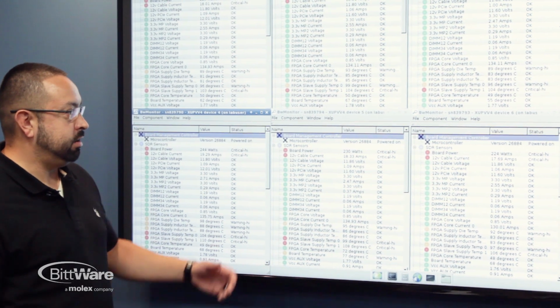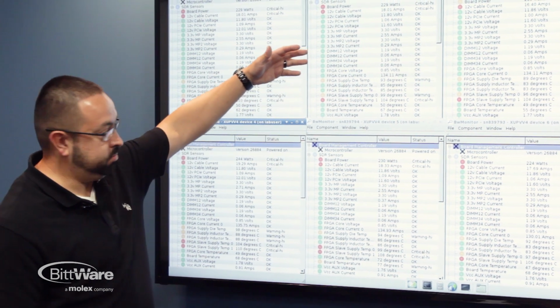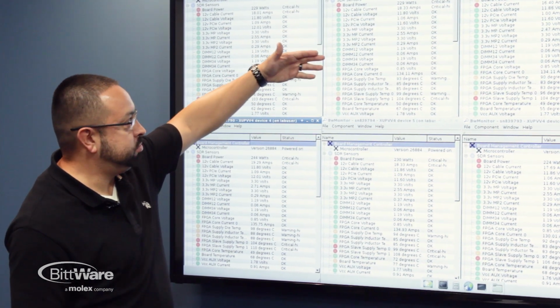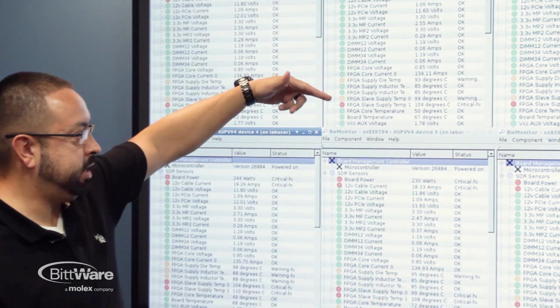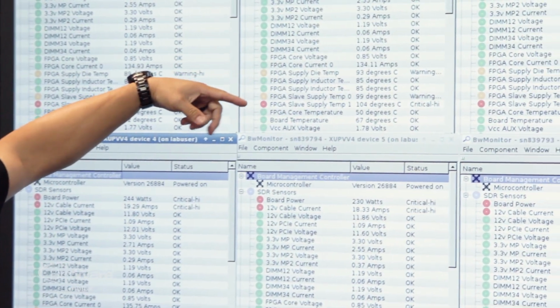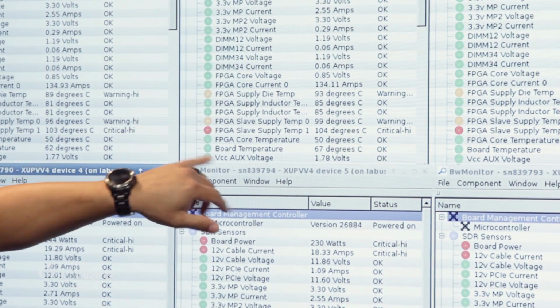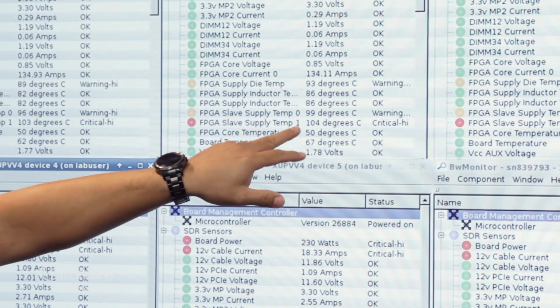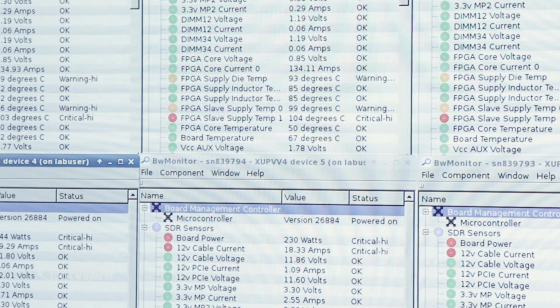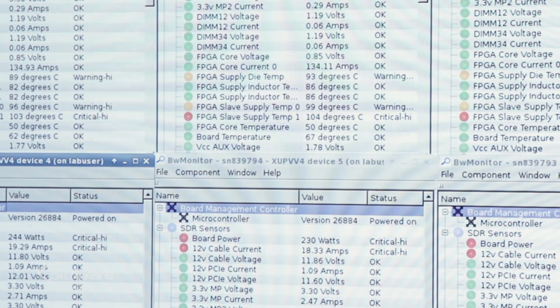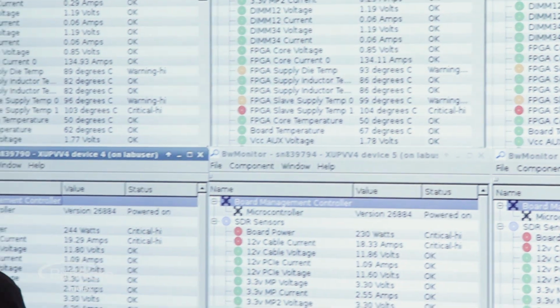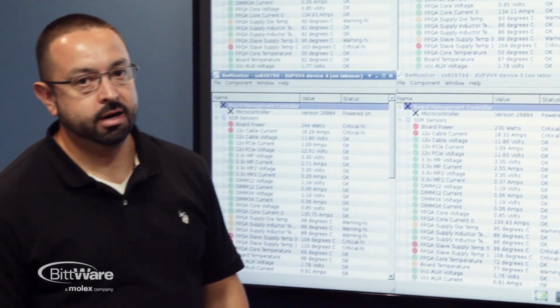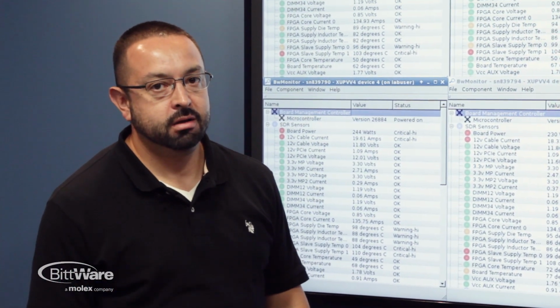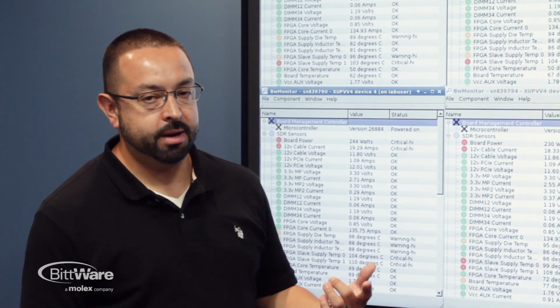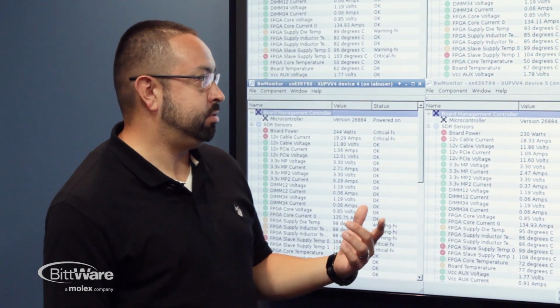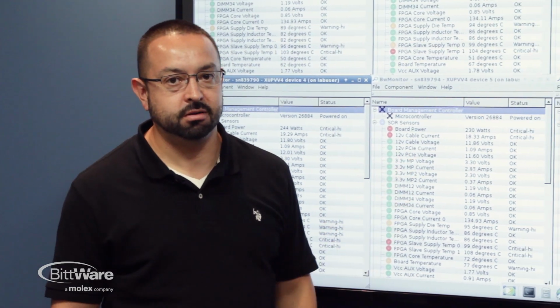If you're looking here at our BW monitor BMC interface, you can see of all these temperatures, the power supplies are going to eventually be the limiting factor. With the slave supplies, mostly slave supply temp 1 usually is the highest, so it's about 104 degrees right now. I think the max on that is about 120 C. So what we're trying to accomplish with the liquid cooling on the XUPVV4, not just the FPGA but also the power supplies, is to remove that limiting factor on the power supplies themselves.